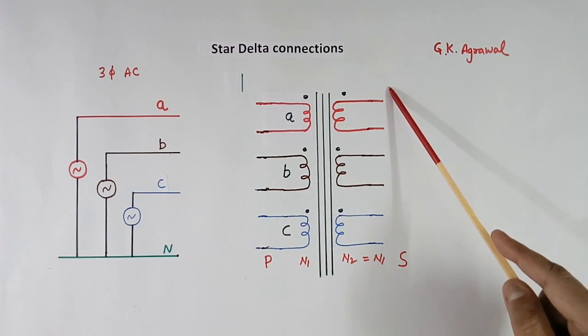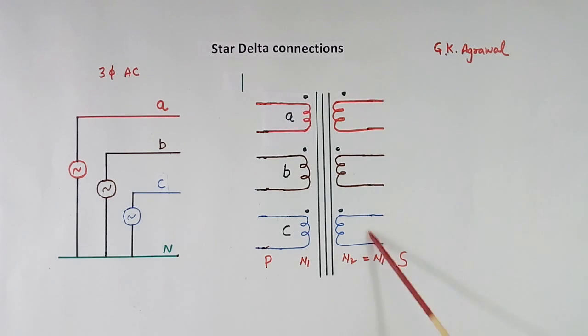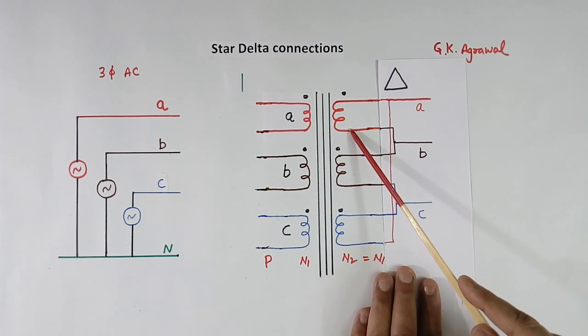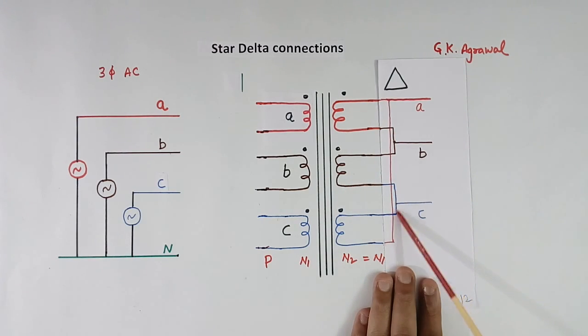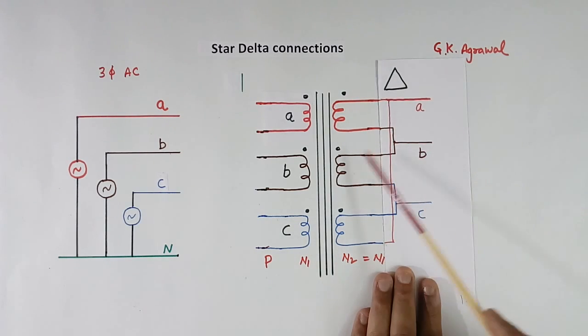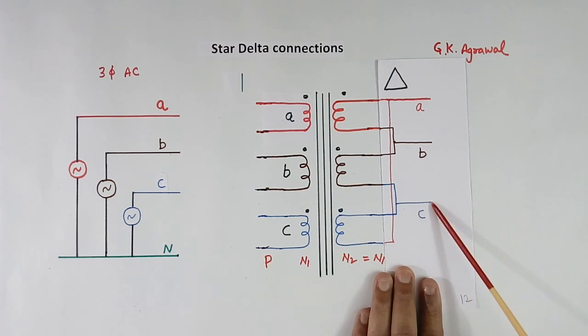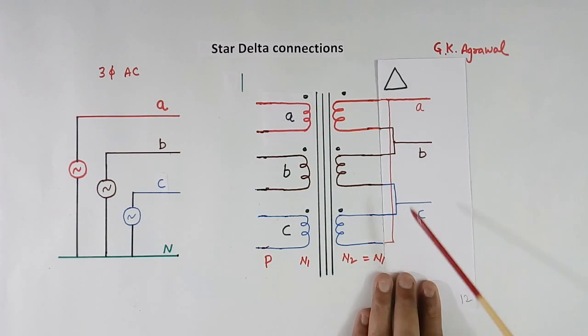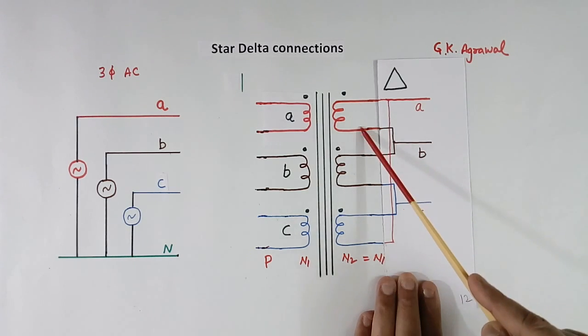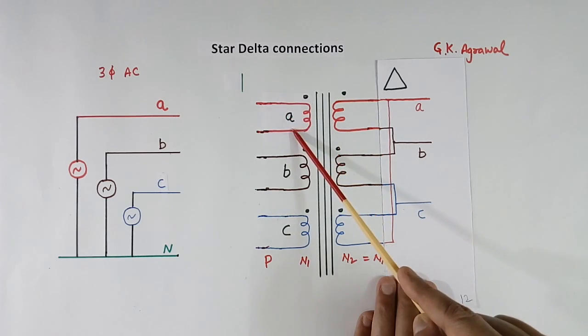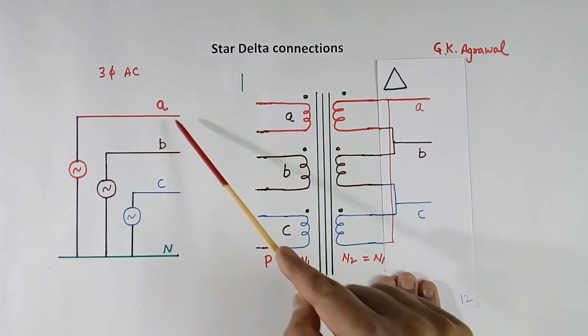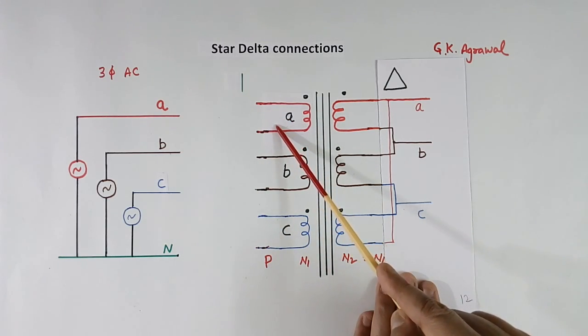Now we will see how to make delta connection of the transformer secondary. In this delta connection, the windings are looped: this wire is connected here, this wire here, and this wire here. The marking terminals are A, B, C — so we get outputs A, B, C with no neutral. If turns are equal and the primary is connected in star, this secondary delta voltage will equal the phase voltage. If the primary is connected line to line, then it will be root 3 times.